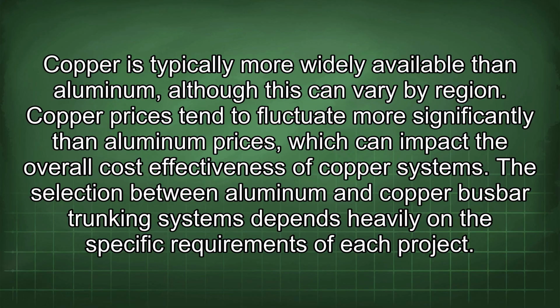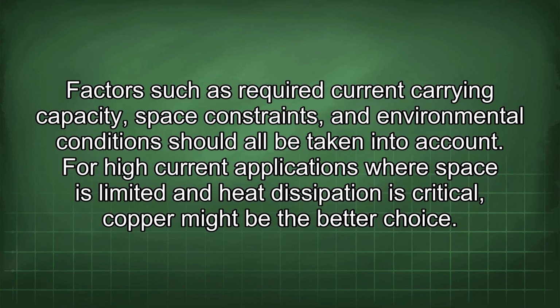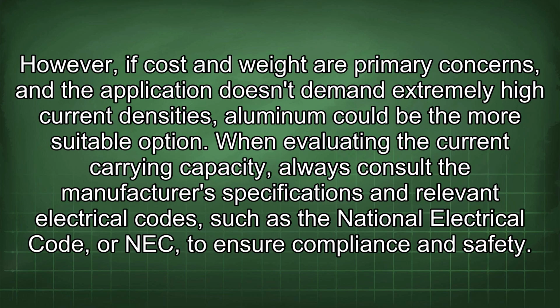The selection between aluminum and copper busbar trunking systems depends heavily on the specific requirements of each project. Factors such as required current carrying capacity, space constraints, and environmental conditions should all be taken into account. For high current applications where space is limited and heat dissipation is critical, copper might be the better choice.